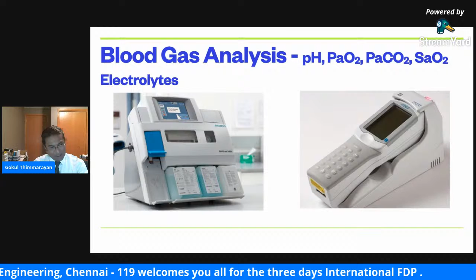Such an efficient device which could analyze and give us hundreds of parameters, and similarly there are hundreds of physical principles involved in it. To discuss it in detail, each one would be a separate topic in its own right. So rather than that, let me discuss a few common principles which are utilized to analyze and give us the results. To analyze oxygen, it utilizes the Clark electrodes or polarographic electrodes, fuel cells, paramagnetic analyzer, and the Severinghaus electrode, with various electrolytes and solutions, IR absorption, UV analyzer, Raman effect, mass spectrometry, all the things that we discussed before. All these are customized and made so efficient to get compressed into the device, where it does the analysis and gives us the report right away in a couple of minutes.